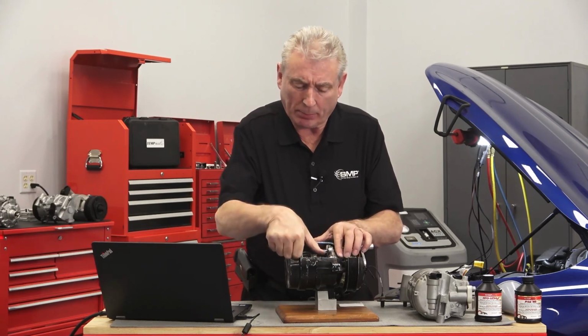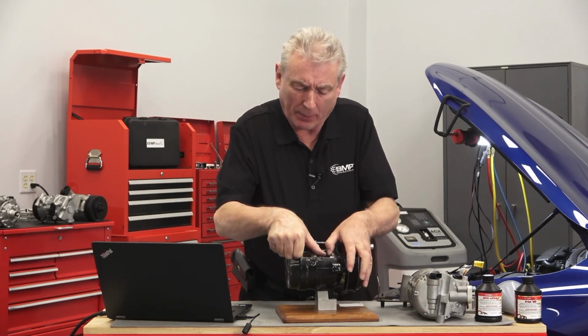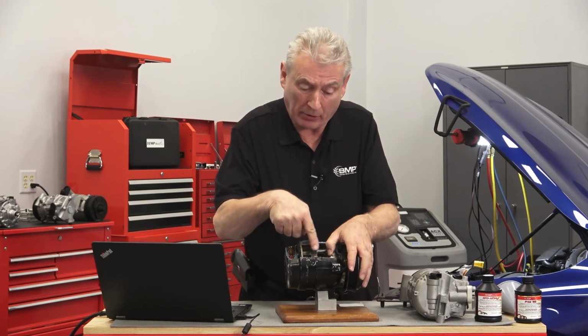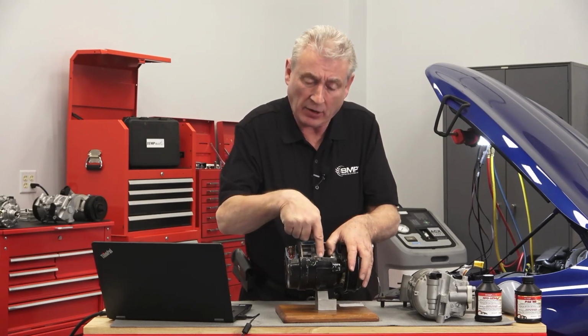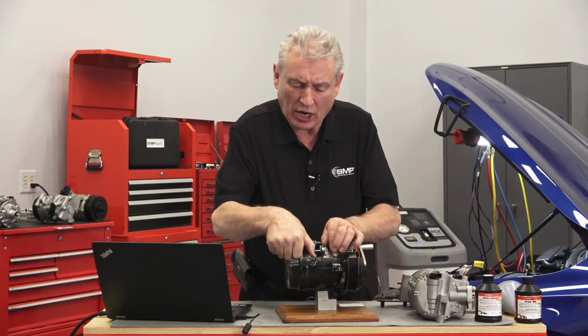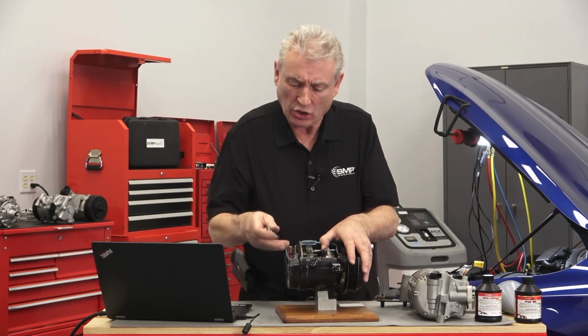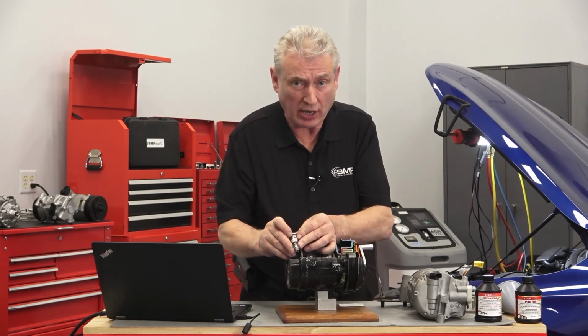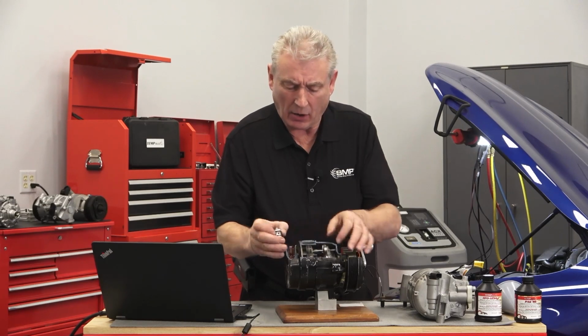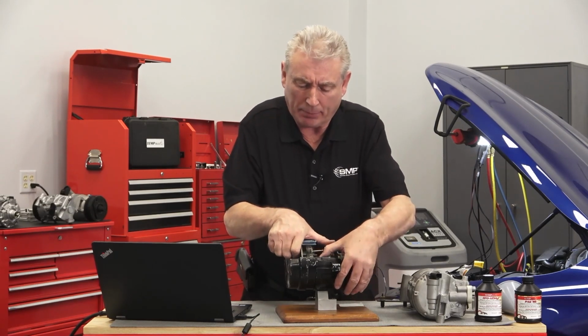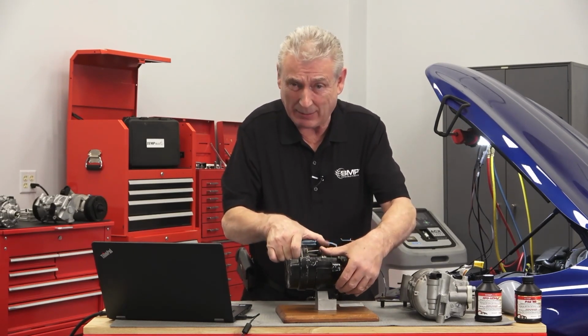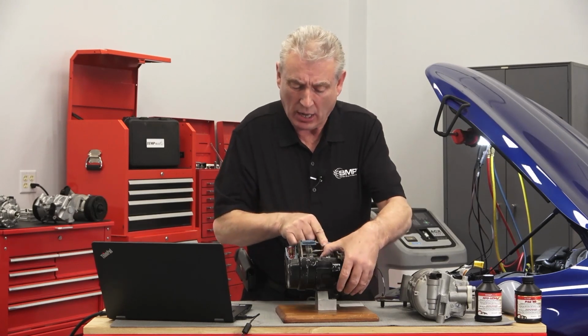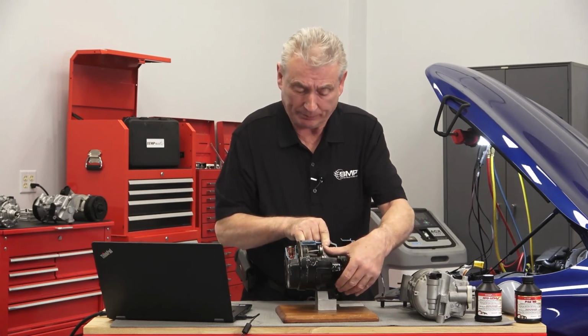By changing the pressure acting on the rear of the pistons, changing the pressure drop from the top side to the underside of the pistons, I can change the angle of the swash plate. So by monitoring suction side pressure, which is a function of the heat load, I can change the pumping displacement of the compressor to seamlessly, gradually, smoothly match the heat load on the system, right?